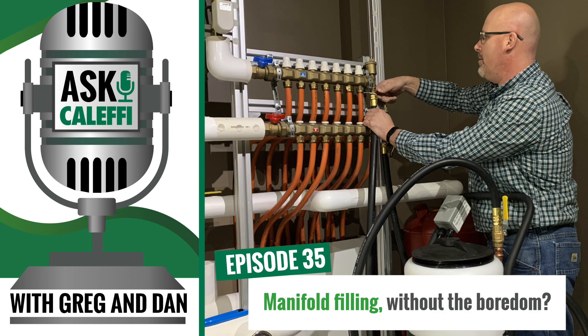It's not included in our instruction manual how to flush and fill the manifold. We've got instructions on how to install it and how to balance it, but nothing on flushing and filling. Probably because there's really no direct set of instructions you can follow — there are so many different ways you can do it. Water takes the path of least resistance, so there isn't an exact set of steps. You kind of have to be a little creative.